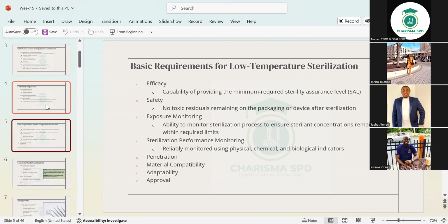The reliable monitoring using physical, chemical, and then biological indicators, which you get to know when you go to the field. We have biological indicators that are more like little bottles that we actually put in the instruments, and at the end we incubate to see whether they were positive or negative, whether the process was good. And we have the chemical ones that are like strips that we put in the trays, and then some are like tapes that we tape around the wrapped instruments. They are all indicators that we need to use.